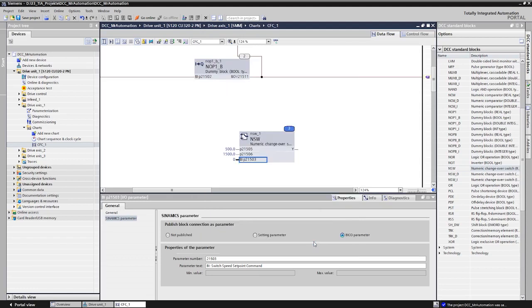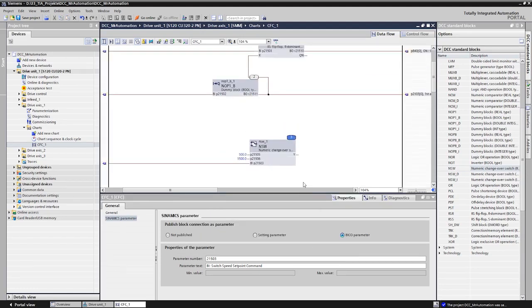The last step is the transfer of our speed reference values to the speed controller of the basic system. For this, it is important to mention that all reference value signals are transferred in SINAMICS as percentage-related values. In order to convert our absolute speed values into the corresponding related value, we read in the reference value, divide the absolute value by this reference value, and obtain the appropriate percentage reference value.